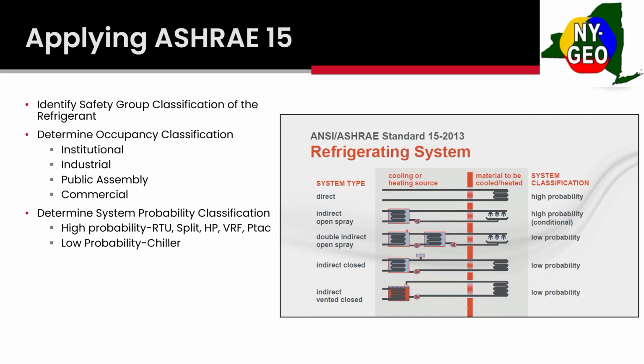Your system probability, that is your equipment. Most equipment, you can see, is high probability. That's your rooftop units, splits, heat pumps, VRF, and PTACs. Basically, a high probability system is one where, if there's a leak in the system, it has a more likely chance of entering the occupied space. So if a rooftop coil leaks, that's going to go straight into the building. Or if a VRF system leaks, that pipe's going to leak into occupied space.